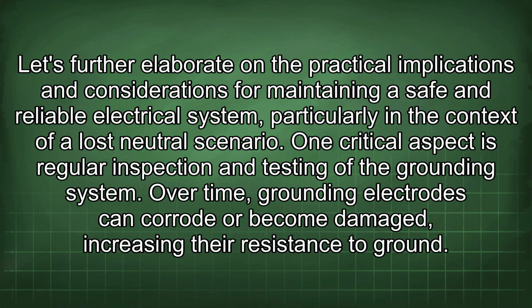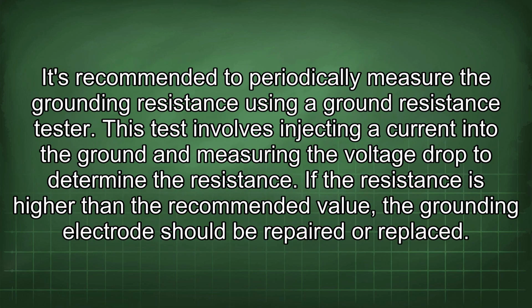Let's further elaborate on the practical implications and considerations for maintaining a safe and reliable electrical system, particularly in the context of a lost neutral scenario. One critical aspect is regular inspection and testing of the grounding system. Over time, grounding electrodes can corrode or become damaged, increasing their resistance to ground. It's recommended to periodically measure the grounding resistance using a ground resistance tester. This test involves injecting a current into the ground and measuring the voltage drop to determine the resistance. If the resistance is higher than the recommended value, the grounding electrode should be repaired or replaced.